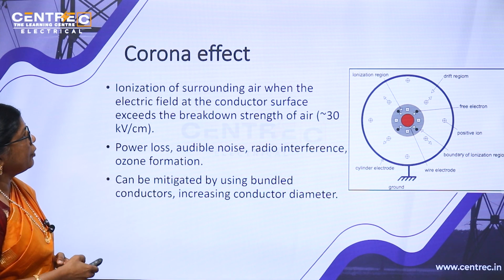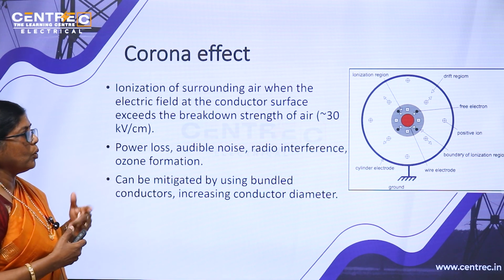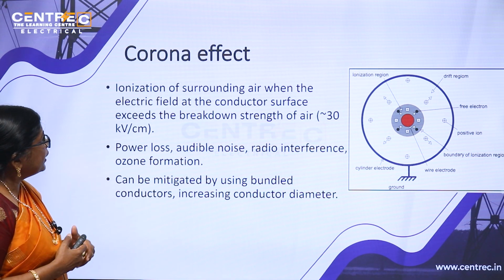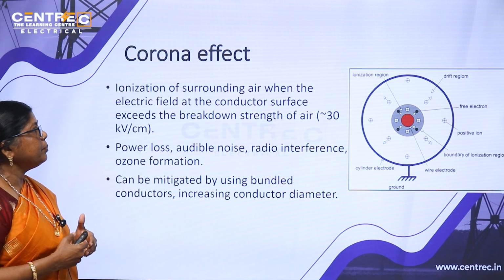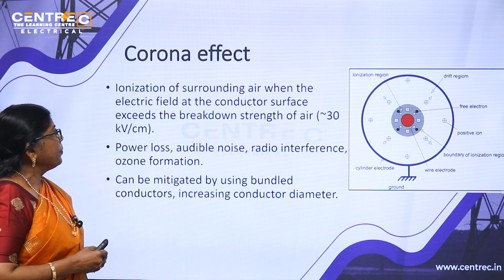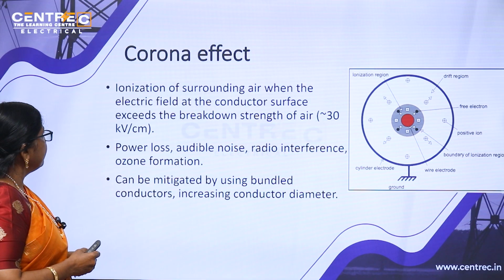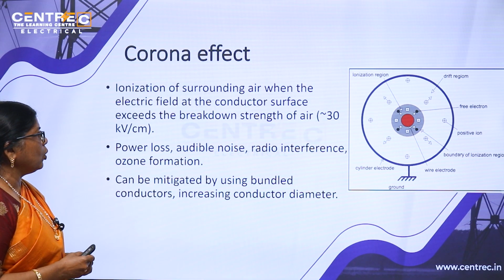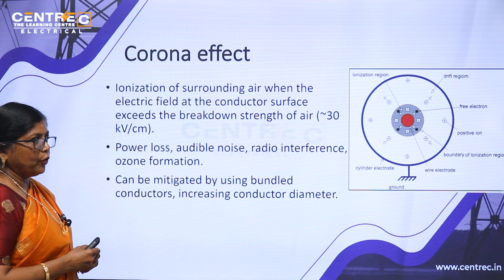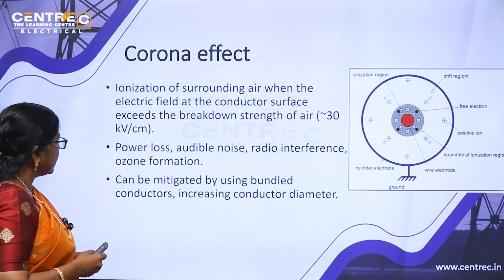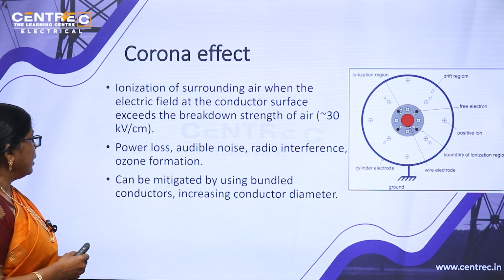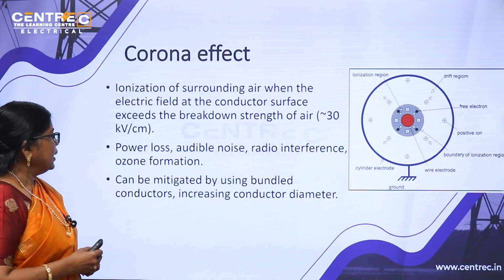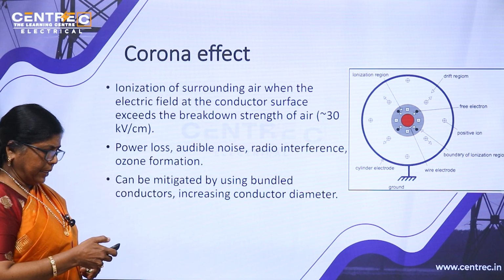Then we have Corona effect, the ionization of surrounding air when the electric field at the conductor surface exceeds the breakdown strength of air, 30 kV per centimeter. Power loss, audible noise, radio interference and ozone formation are the consequences. It can be mitigated by using bundled conductors, increasing conductor diameter, etc.